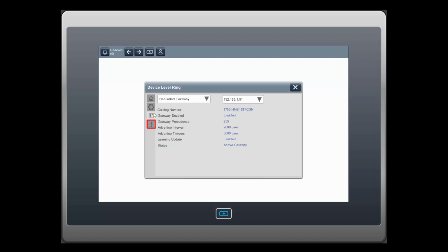The network fault screen provides details about network health. When a network fault occurs, it will indicate the fault type and fault location. Any fault clear should be performed via advanced user tools like Device Manager or the Logix Designer add-on profile. When a network fault occurs, the faceplate will indicate one of the following faults.